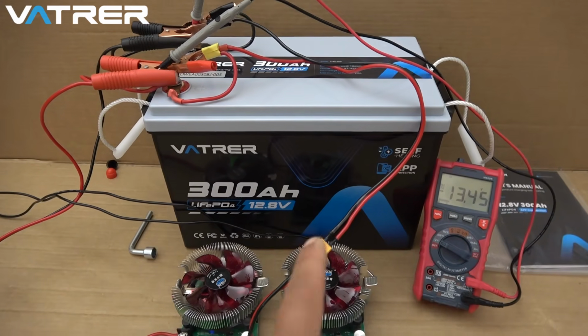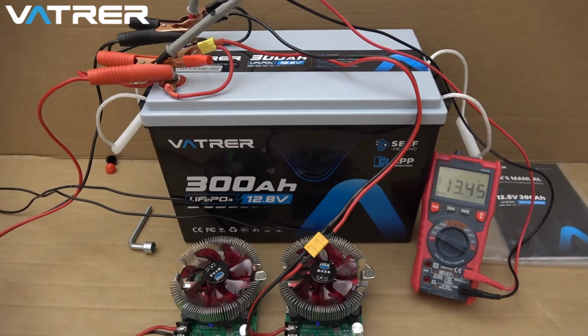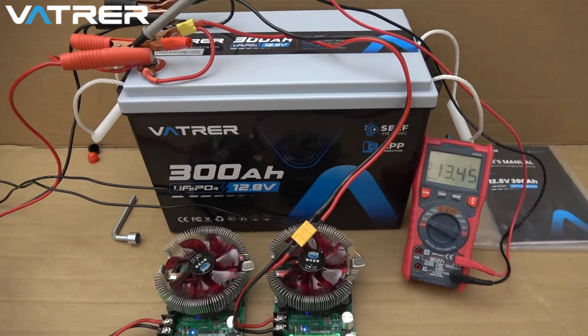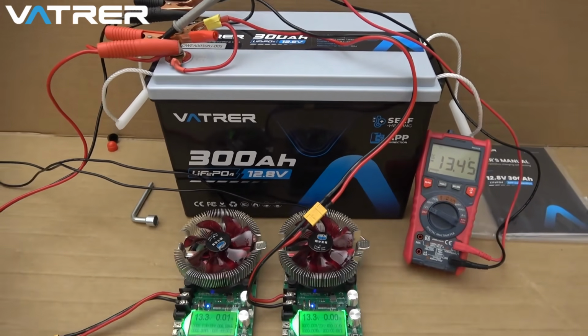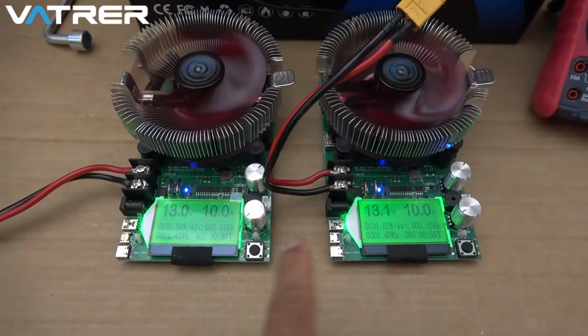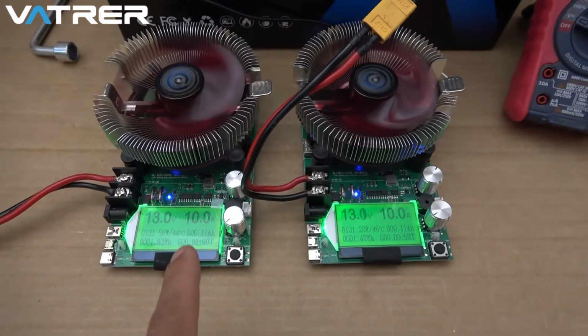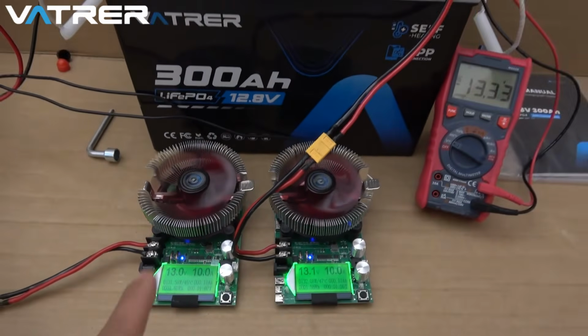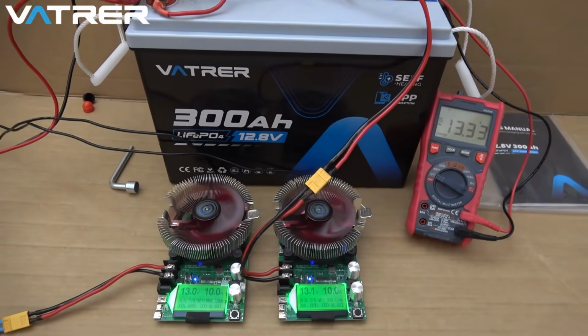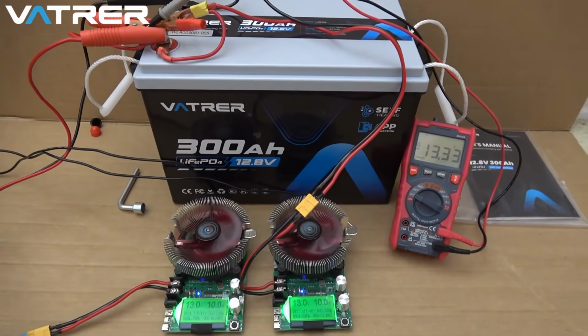I have charged the battery to 100%, and it's at 13.45 volts. It's time to do a discharge test. We've got 2 DC dischargers here, each can do 10 amps, so a total of 20 amps. The battery is 300 amp hours, so it's going to take about 15 hours to finish.